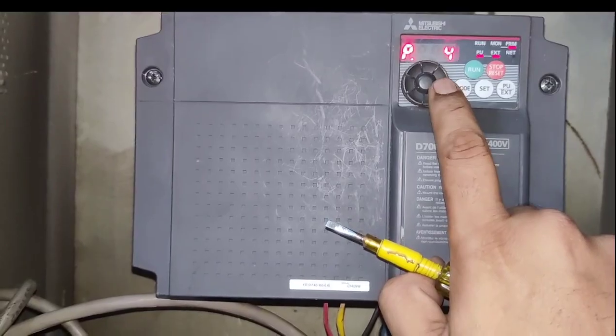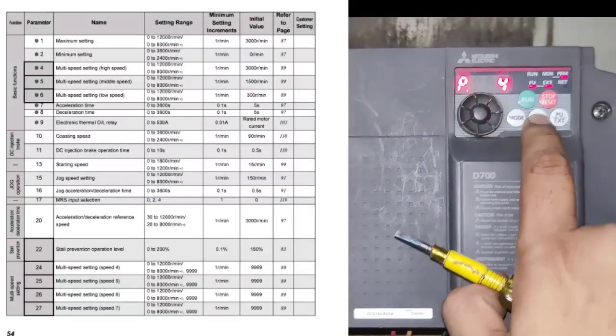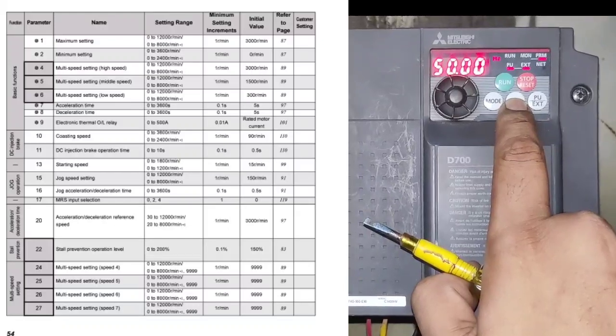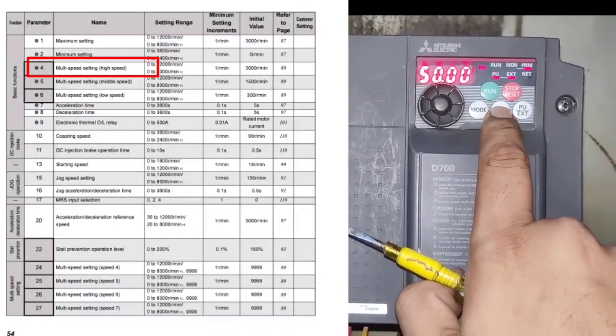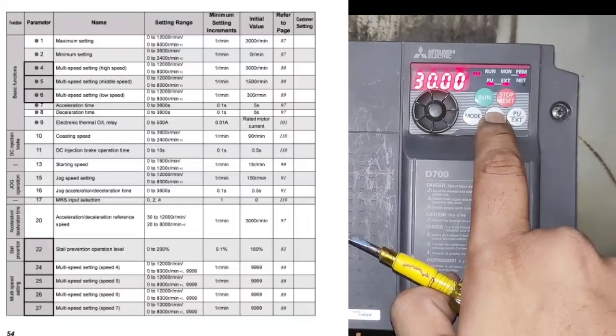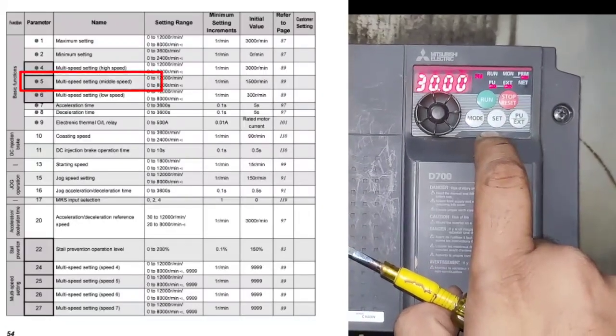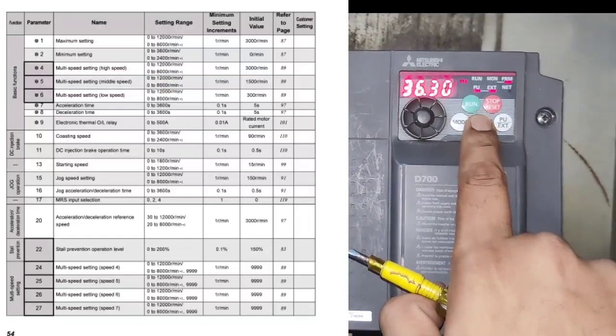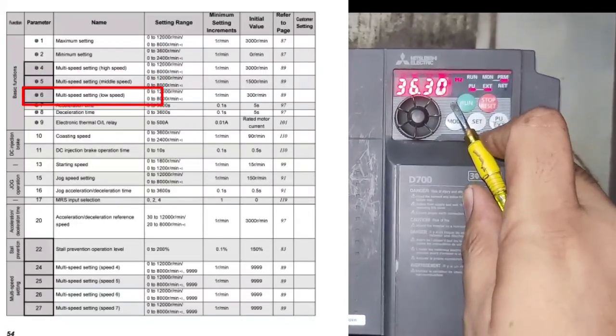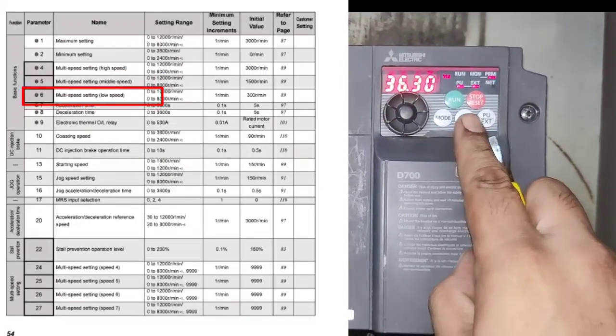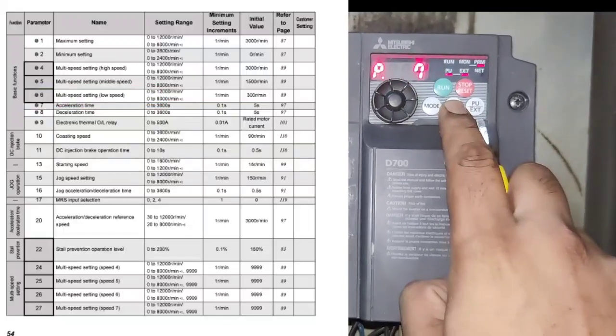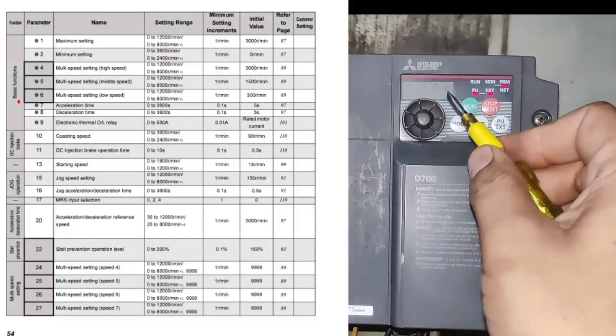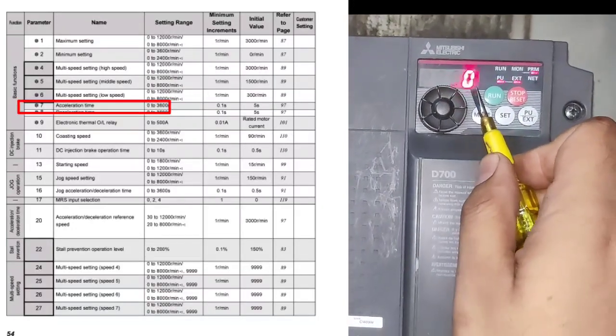Next parameter is P4. If you want to run your motor in multi-speed function, P4 is for high speed — we set 50 Hz. P5 is for middle speed — we set 30 Hz. P6 is for low speed — you can manually set whatever frequency you want to run at.